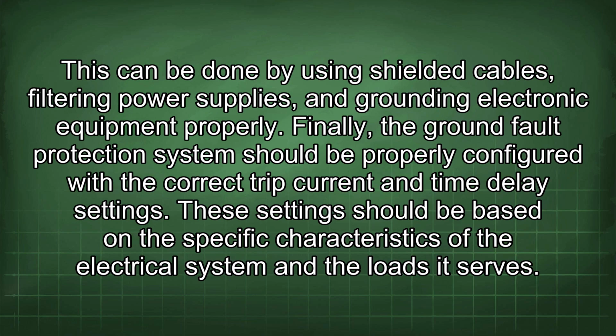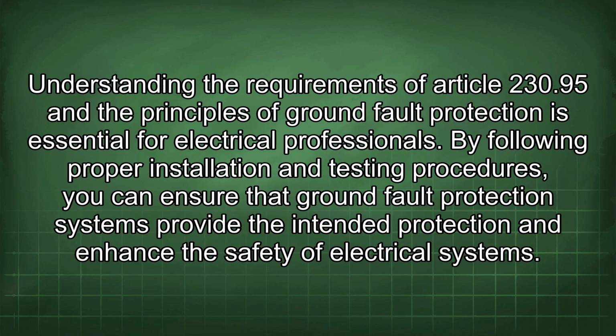Finally, the ground fault protection system should be properly configured with the correct trip current and time delay settings. These settings should be based on the specific characteristics of the electrical system and the loads it serves. Understanding the requirements of Article 230.95 and the principles of ground fault protection is essential for electrical professionals. By following proper installation and testing procedures, you can ensure that ground fault protection systems provide the intended protection and enhance the safety of electrical systems.